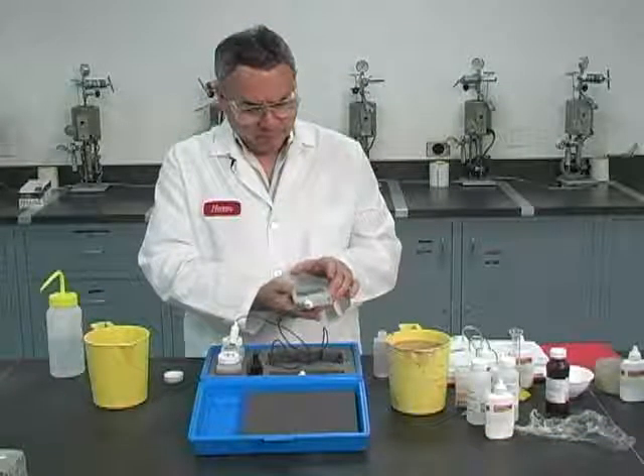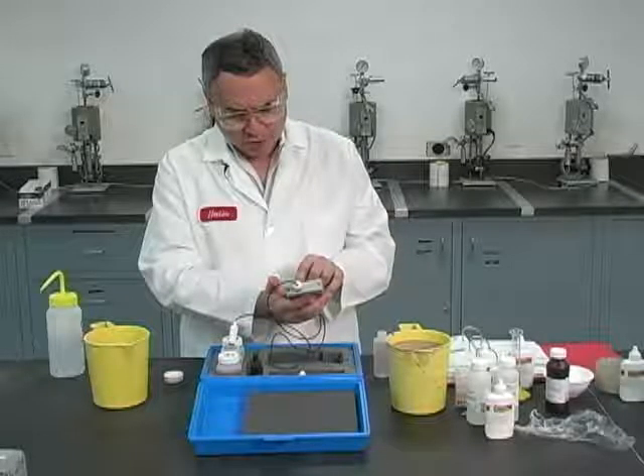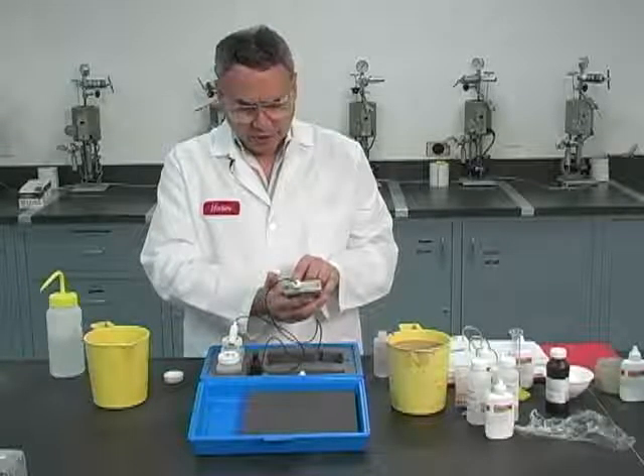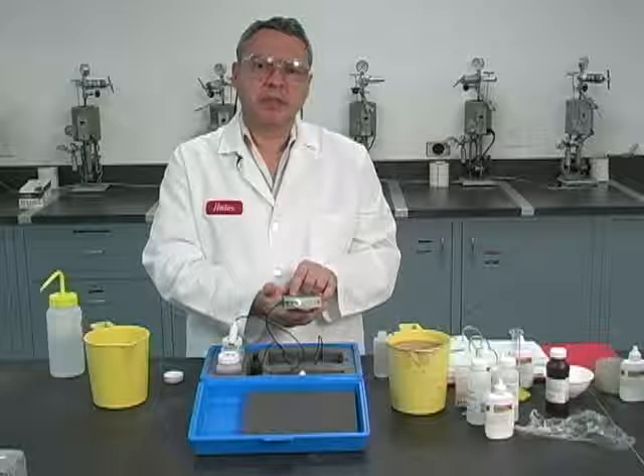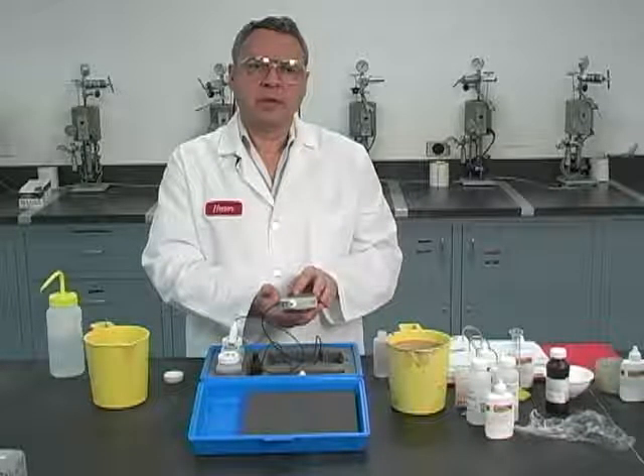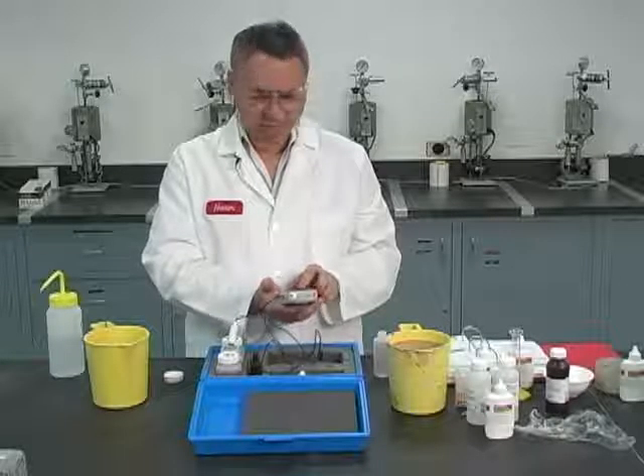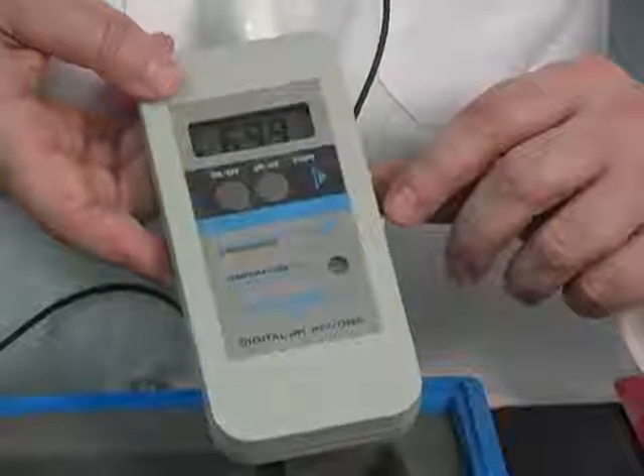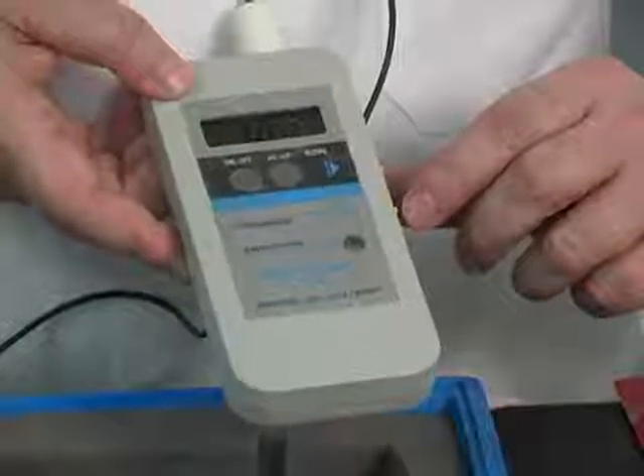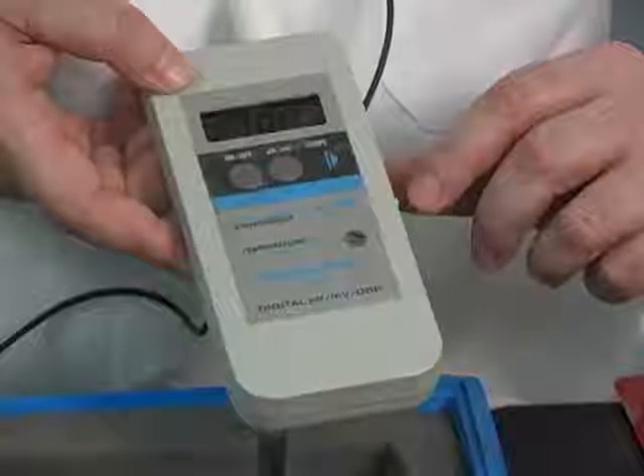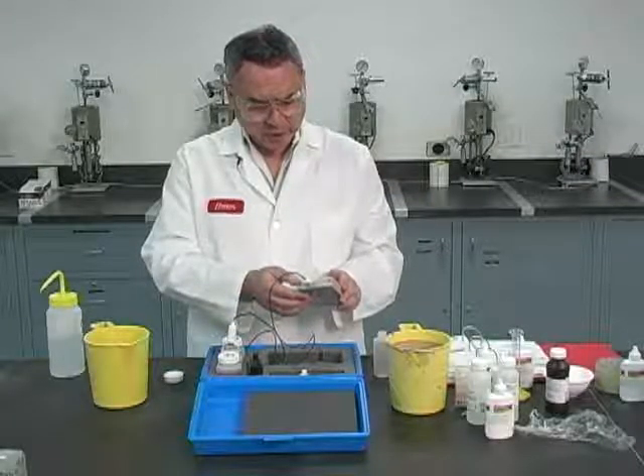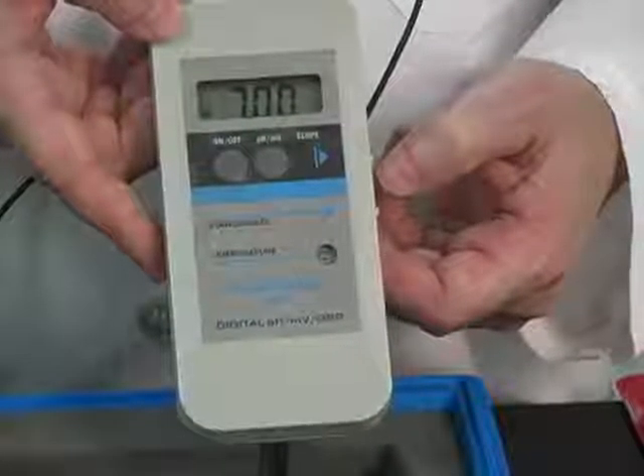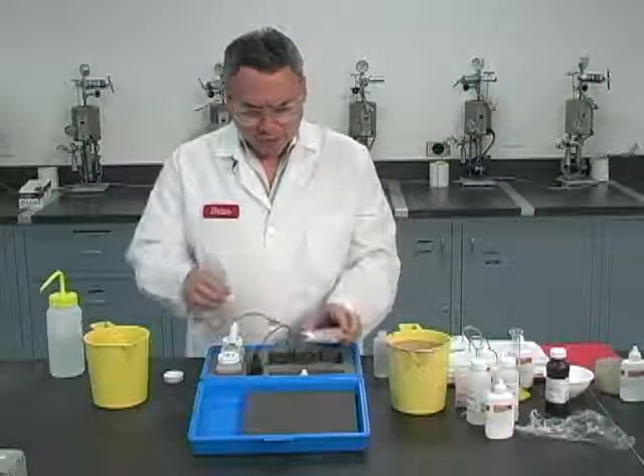So here we are with pH 7. Before the calibration, I checked, and the instrument has the room temperature, which in this particular case is 20 degrees Celsius, corresponds to approximately 70 degrees or 69 degrees Fahrenheit. 7 is the pH of the buffer, so buffer would be a very stable solution. And so what I have to adjust here is one little screw that says standardize and put it exactly in 7.00.